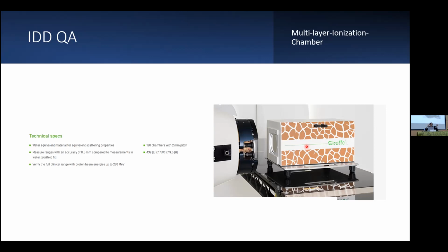So when everything's there, then it's just a film that kind of protects in case something falls so it doesn't fall into the nozzle. They just actually forgot to put that one piece back on. But that has a certain thickness. And if they left it off and you treat it, all the depth doses are going to be off by that thickness. And that's why you have to go in and know what they did, what they took off, put back, and do a measurement that's meaningful so you could check.